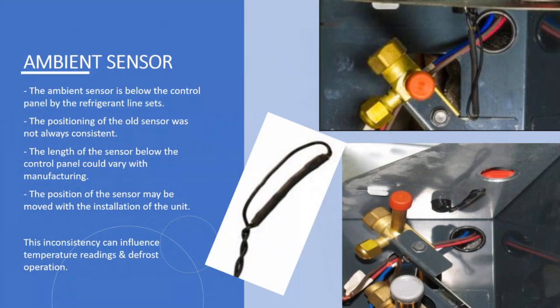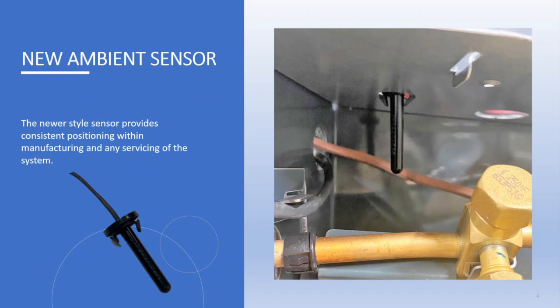We use two sensors to decide whether it needs to go into a defrost or not. So this is a demand defrost system. You'll see this on all Trane unitary equipment and most ductless equipment, where you're going to see two sensors, one of them being an ambient sensor. This is our older version of the sensor. As you can see, sometimes it could be hanging down or tucked this way. So it was changed to this sensor in the last few years so that it was always in the exact same spot for consistency.